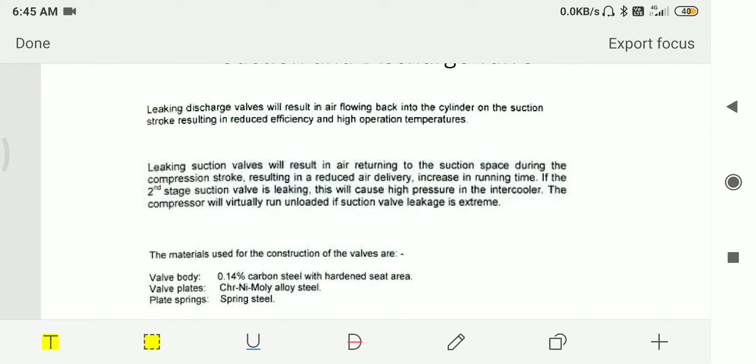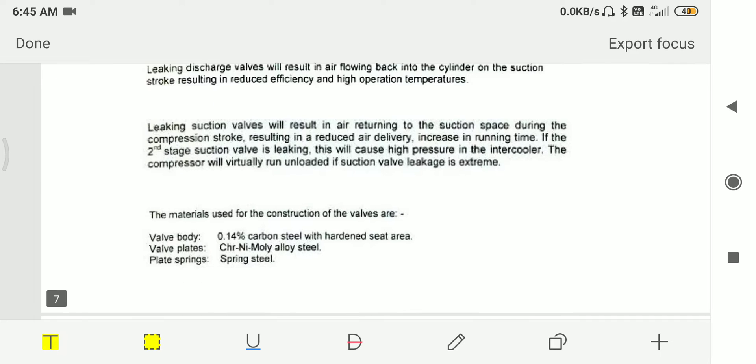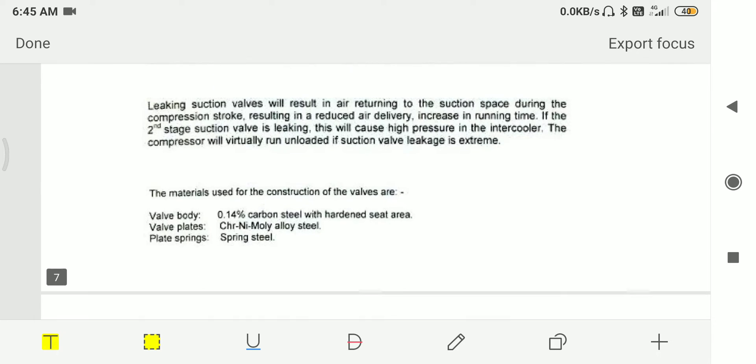If discharge valve is leaking, it will result in air flowing back into the cylinder on the suction stroke, resulting in reduced efficiency and high operating temperatures. If suction valve is leaking, it will result in air returning to the suction space during the compression stroke, resulting in reduced air delivery and increase in running time.